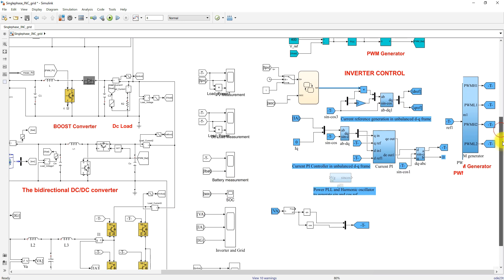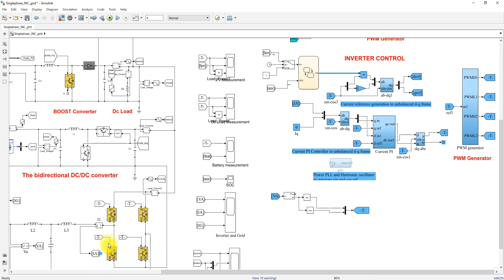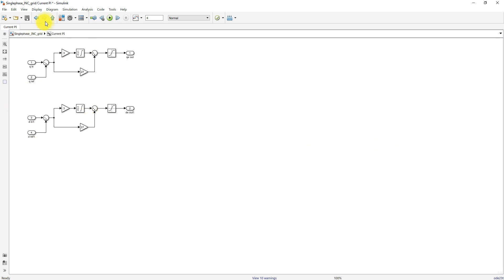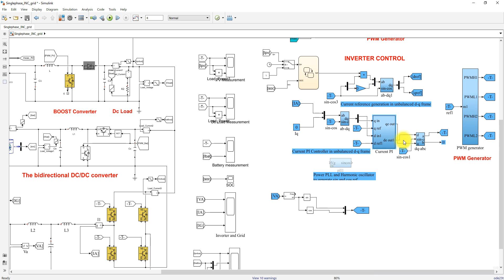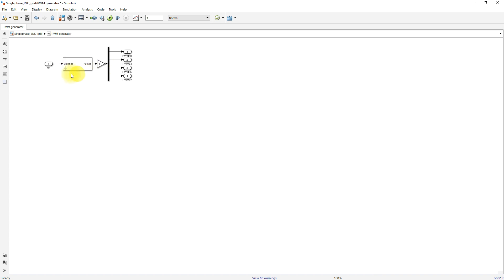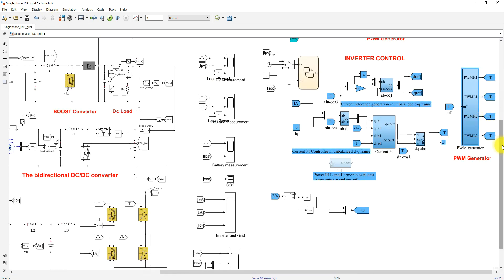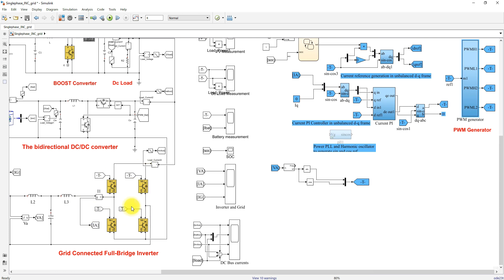The inverter current is measured and converted into DQ form. The DQ form of the actual inverter current and the reference current are processed via a current controller, which generates the control voltage in DQ form. This is converted into alpha-beta form, and processed via a sinusoidal PWM generator, which generates the pulse for the inverter to control the current flow. The inverter operates in bidirectional mode based upon the conditions of IPV and SOC.